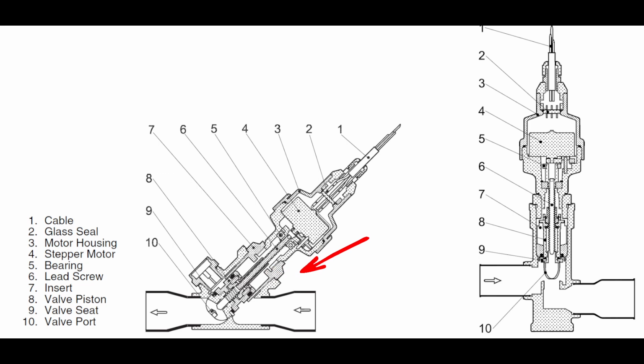That process can be initiated most of the time strictly by power cycling the chiller. So if you fully shut the chiller down and then power it back up, most chillers have programmed in their software to automatically go through a valve calibration at the time of power up. On some chillers, you can do this by cycling the circuit. So every time a circuit is told to specifically turn on, and it's been given an enable command, before it will start the compressors, it will do a calibration on the valves if it's the first time it started up that day. Now, not all chillers will do that, so just be aware that it may only do the calibration at power up, and that's it. And then some chillers will have a manual calibration feature in the controls package.